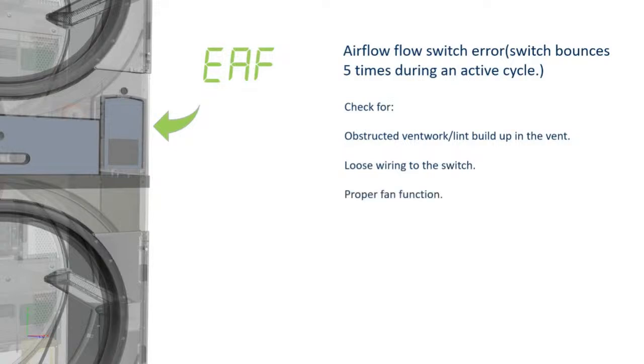Is the fan working like it should? Is the fan motor turning? Is it drawing air in? And finally, check the mechanical portion of the switch, the vane and the armature that holds it down. That's one of the three error codes.